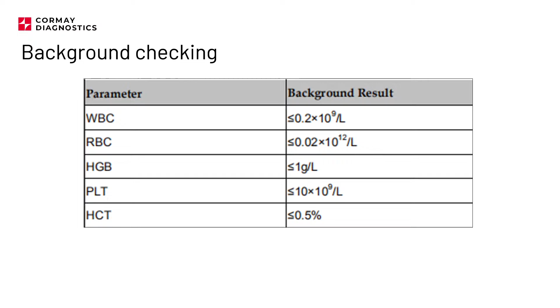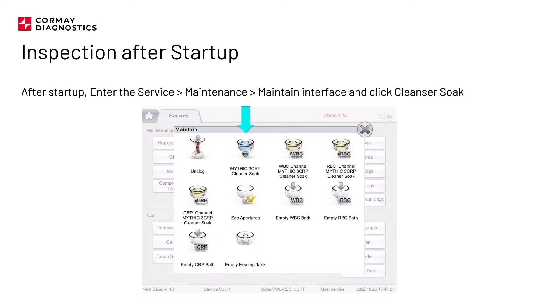if this is the first startup, it's also recommended to do the Mythic 3CRP cleaner soak. What you need to do is take this hypochlorite solution and put it to the sampling needle. Of course, this is an automatic process. You press here, the analyzer shows you an additional message on the screen, and then you need to aspirate. The analyzer will aspirate this hypochlorite solution, and it will be distributed through the system and clean the system. So this is it. Please remember to do the cleanser soak during the first installation.